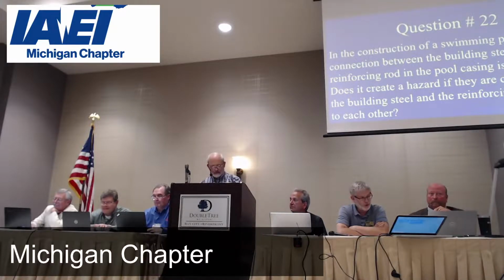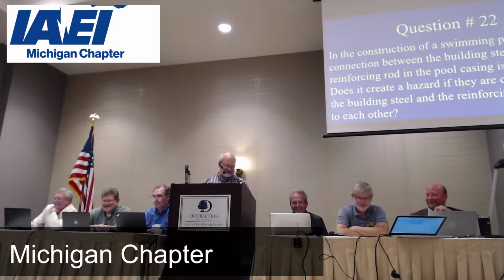grounding electrode system. So extending that pool bonding back to the building would really make the pool a super target for any stray currents or ground fault current that may be introduced on the grounding electrode system, thus potentially introducing safety hazards to the occupants of the pool during events such as lightning-induced stray currents, or maybe a high voltage line dropping down on the secondary. But it would definitely serve as a great grounding electrode, just I don't think I want to be in the pool whenever that happens. Questions, comments? Everybody agrees? Sure, I believe that, but okay.